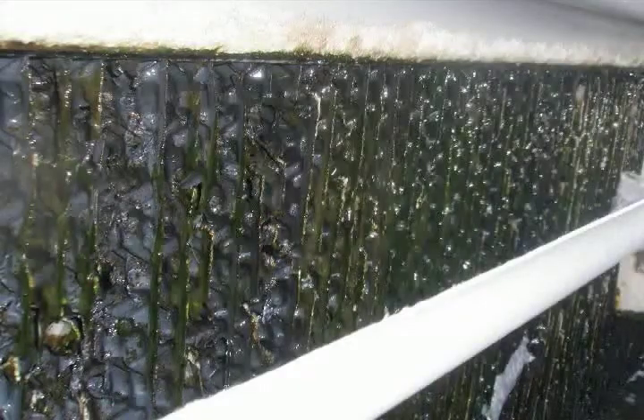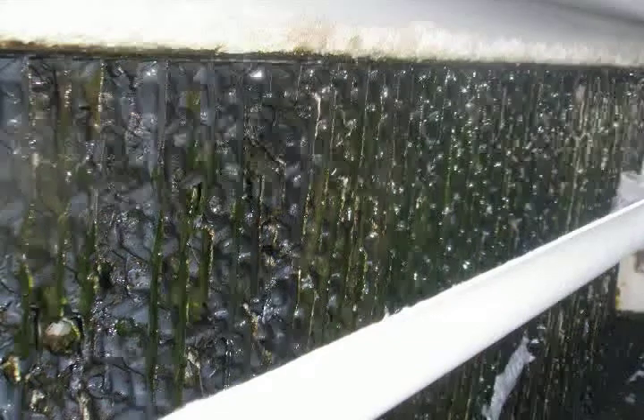Obviously, cooling towers are perfect breeding grounds for biological activity, as well as algae. Algae needs sunlight on top of everything else, but when you think about it, a cooling tower has the heat. That's what you're trying to remove, so it's a warm environment. It's got water. If you ever sat or stood next to a cooling tower, you get sucked in, because it's basically an air washer. So it's sucking in nutrients, materials, suspended solids. So you're feeding it, you've got warmth, and you've got water. It's a perfect breeding ground for biological activity.